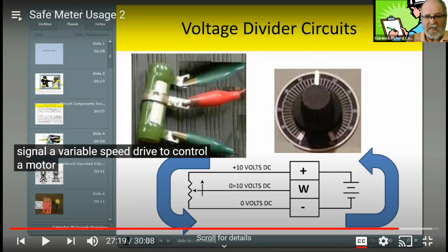So as I'm looking at this, I'm going to do some annotating here. I'm going to be putting a little box around it. Say this was a DC motor controller or a VFD, a variable frequency drive, and you want to be increasing and decreasing the speed of it. It's got some terminals on it called speed reference or speed input, and it's going to have like 3 terminals like this. But internal to this VFD is a power supply. It's a 10-volt power supply.